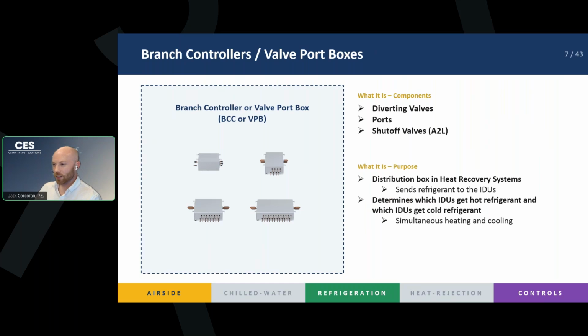And this device also allows you to get your simultaneous heating and cooling. The powerful part of VRF with heat recovery is that you'll have zones on the shady side of the building and the sunny side of the building that need heating and cooling at the same time. This box is what allows the hot vapor to go to the heating zones, and it allows the low pressure liquid to go to the zones that need cooling. It's basically just your distribution box that allows refrigerant to go one place or the other.